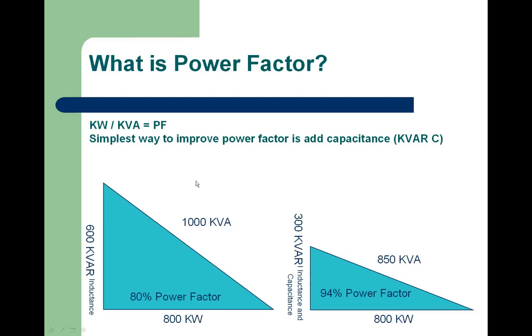So an example of how we do some of the hydro bill savings, we look at a plant here, and on the left-hand side, we have a facility that's using 800 kilowatts of power to run their system, and their kVA is actually 1,000 kVA. So if we take the 800 and divide that by 1,000, we end up with an 80% power factor. Now, to get our 1,000 kVA, this particular site is actually using 600 kVARs of inductive reactance. That would be the magnetizing power required to turn a motor, make a transformer operate, and etc.